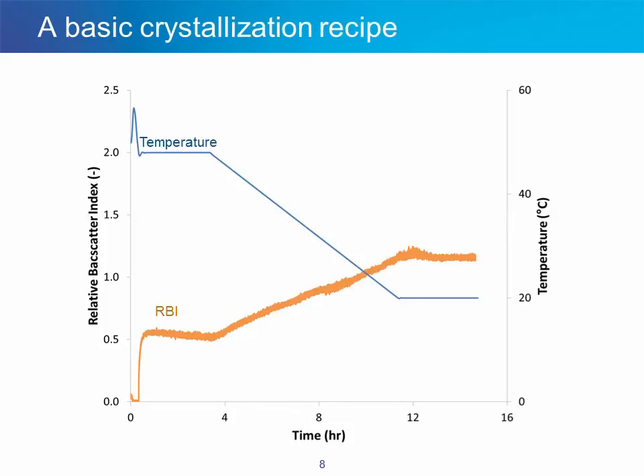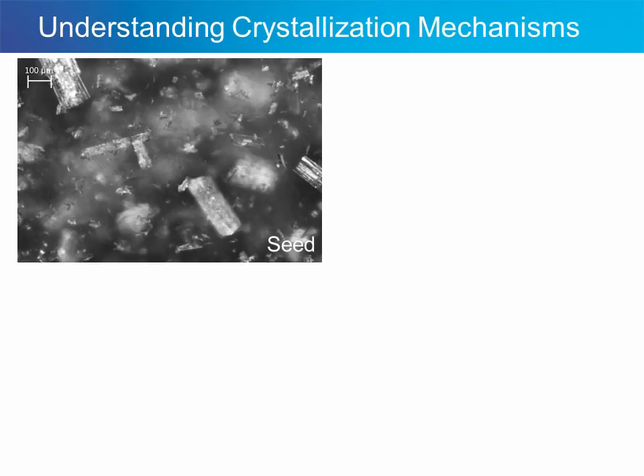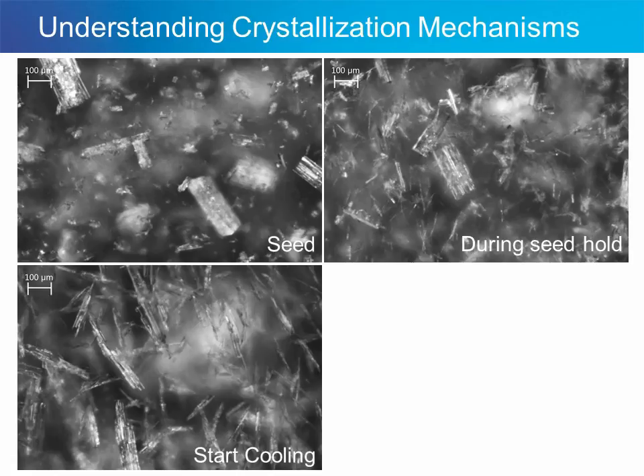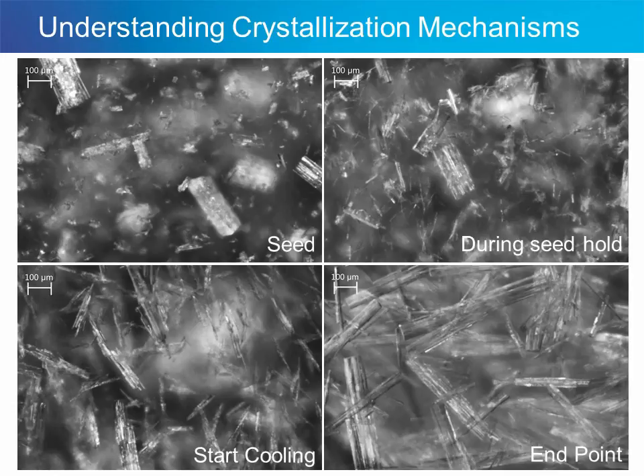In this example, we follow a basic crystallization recipe where we hold temperature constant, add seed, wait until the seed holds and reach a steady state, then decrease temperature inducing crystal nucleation and growth, followed by a hold period at the end to maximize yield. The RBI signal indicates where the seed is added, that the seed holds, identifies when the seed reaches steady state, tracks the growth and nucleation of the crystals, and indicates when steady state is reached at the end of the process. Looking at the microscope images for each of these points, we can see what the seed looks like, observe a secondary nucleation event during the seed hold, see what happens as cooling starts and crystals grow, and see what the crystals look like at the end. This combination of real-time microscope images with RBI is a powerful technique.